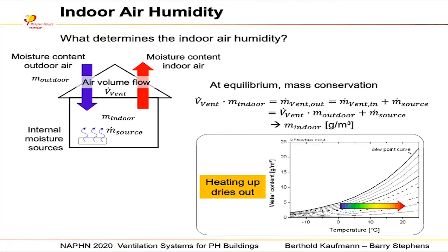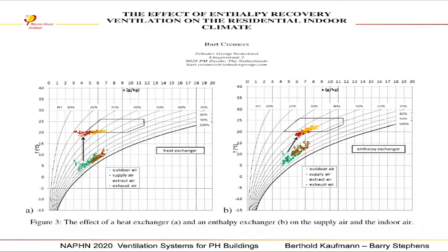And the other point right now, back to air humidity, is we have to find a balance: not too much air in, air out, and not too low. Yeah, and this is shown again here on this graph. Please be careful not to dry out your people and your building. To demonstrate this, on the left is an HRV, and this box is the comfort box for the relative humidity inside the space. And this is an HRV, and this is an ERV with the very same conditions.